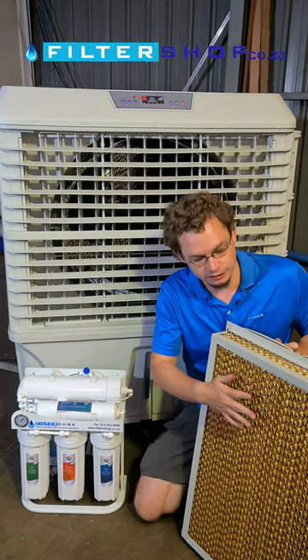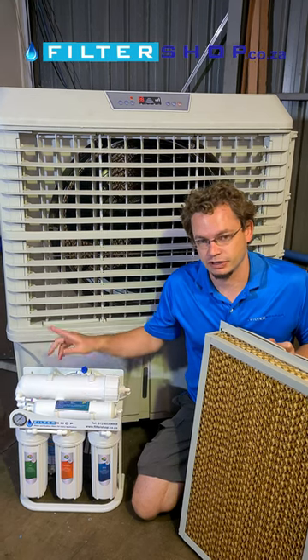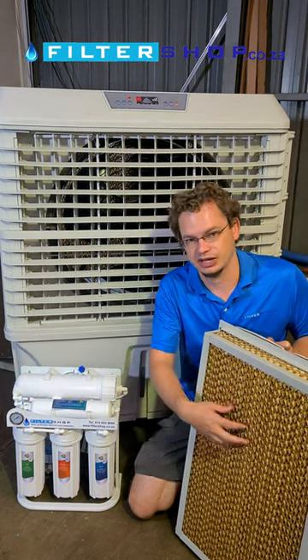The big thing to keep in mind with them is that you need to use good water. So here in our factory we run through a reverse osmosis system with low mineral content to prevent the scale build up in the unit.